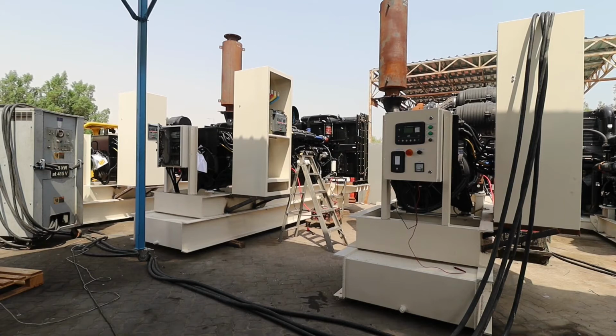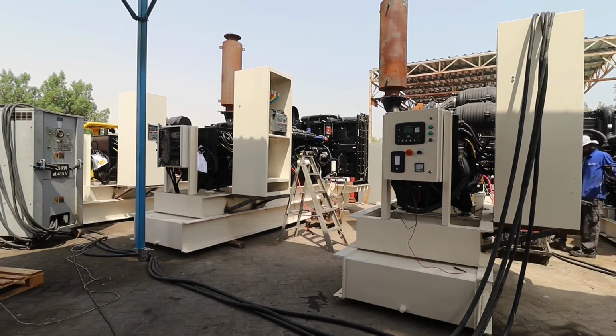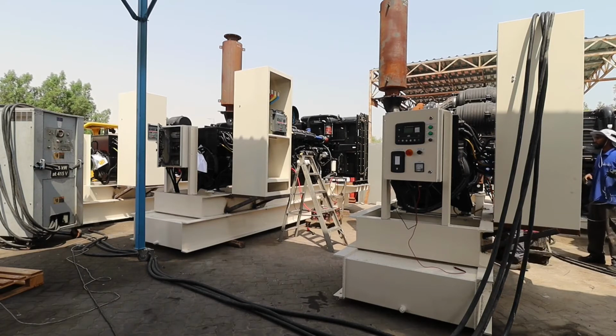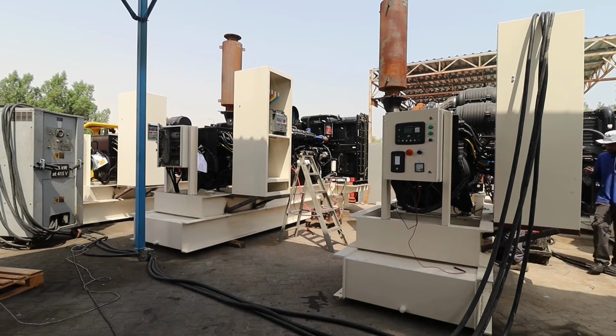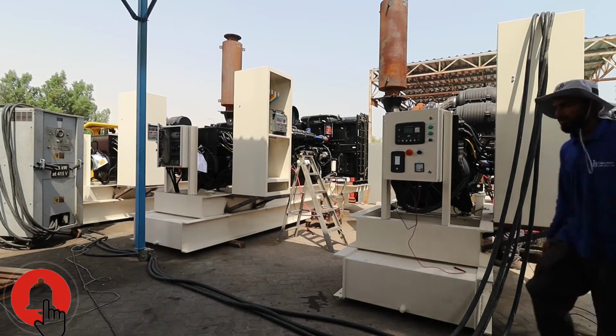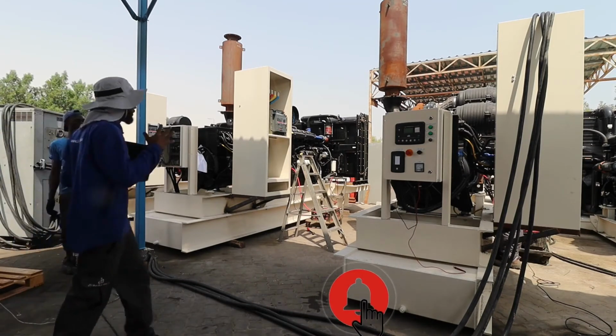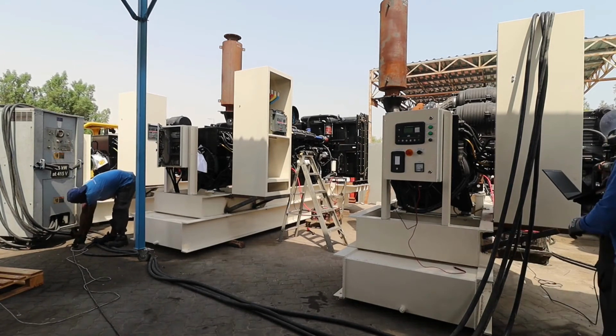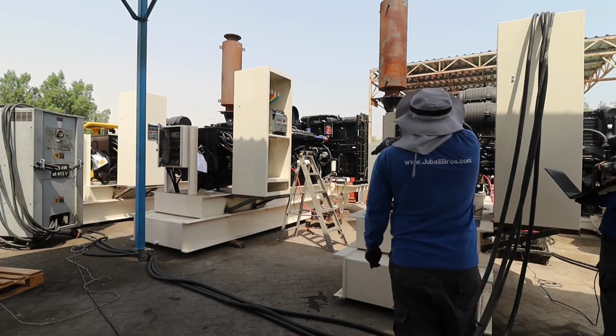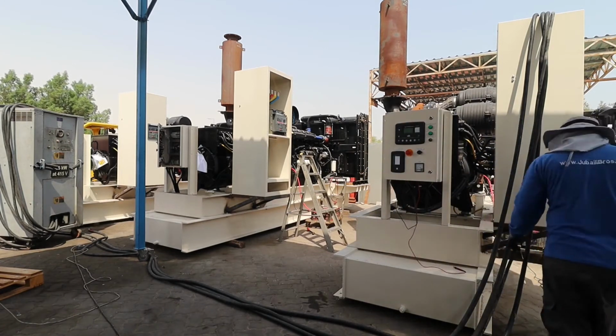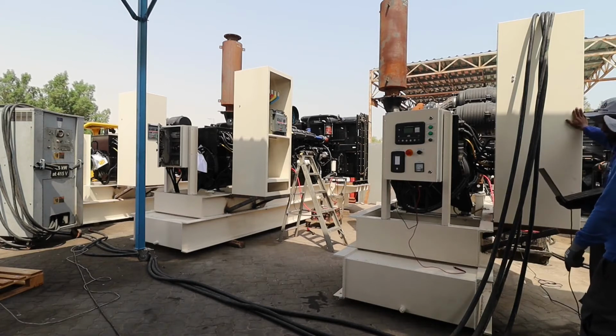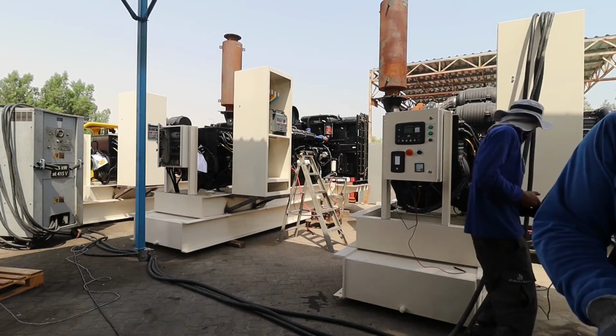So as you can see how difficult it is doing the troubleshooting for the generator itself. Now we're bringing the EST toolkit for the Perkins engine in order to identify exactly what is the fault alarm inside of the ECM. If there is some supply coming, if there is some missing connections and missing information, what we need to check for this trouble. Now is opening the applications for that, if it is communicating also to our laptop.